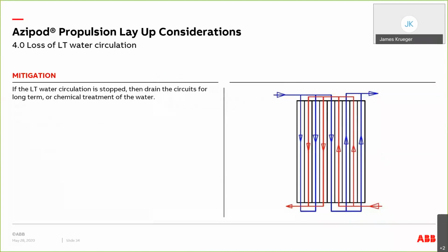On the next slide, I think, yes, we mentioned that if the LT water circulation is stopped, then we recommend to drain the circuits if it's going to be for long term, or there are chemical treatments that can be added to the water. Of course, chemical treatments have to be carefully considered because some may be corrosive to certain components within the cooling system. So it's one of those things that oftentimes chemicals can actually cause additional problems.